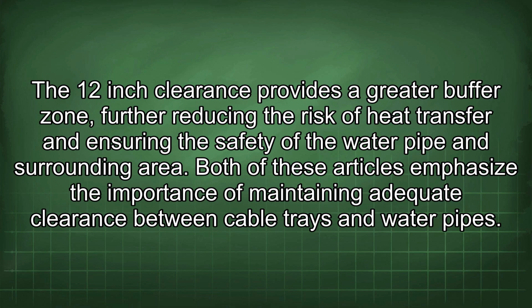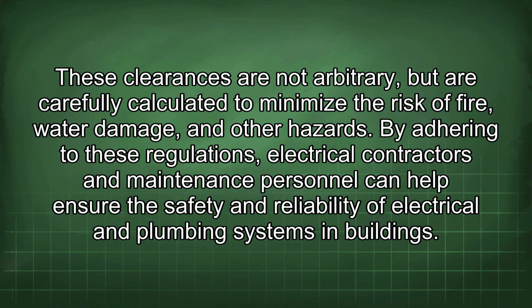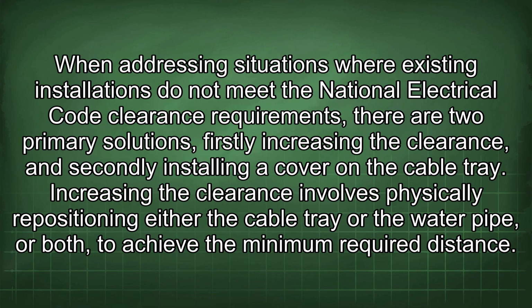Both of these articles emphasize the importance of maintaining adequate clearance between cable trays and water pipes. These clearances are not arbitrary, but are carefully calculated to minimize the risk of fire, water damage, and other hazards. By adhering to these regulations, electrical contractors and maintenance personnel can help ensure the safety and reliability of electrical and plumbing systems in buildings. When addressing situations where existing installations do not meet the National Electrical Code clearance requirements, there are two primary solutions: firstly, increasing the clearance, and secondly, installing a cover on the cable tray.